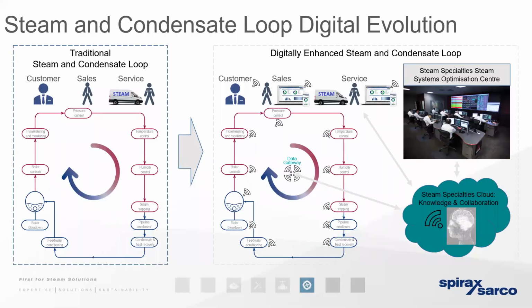So moving forwards, we've also got another challenge that we're addressing at the moment. That's regarding the digitalization of our clients' overall steam and condensate loop. There's a huge opportunity here. It ticks a lot of boxes for a lot of stakeholders on our client's site. So when we think about a traditional steam system, the processors are in many cases capable of sending a signal back from control valves, steam traps, variable speed drive pumps, boiler controls, flow meters, etc., to a variety of PLC or BMS systems for diagnosis on site.